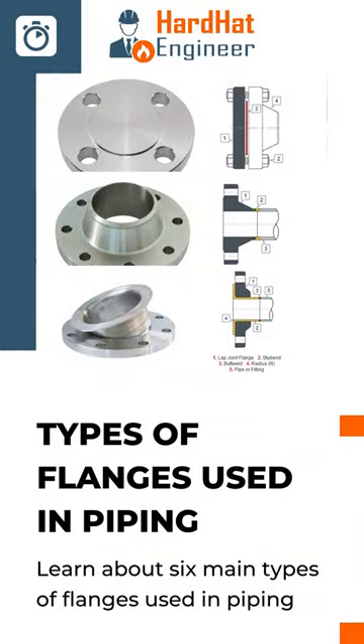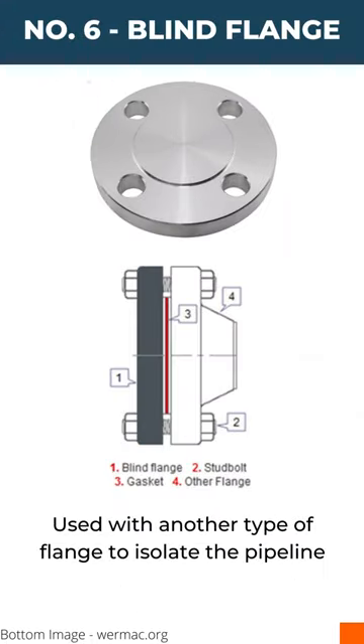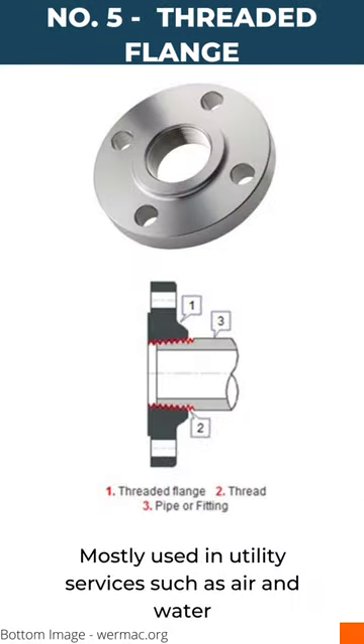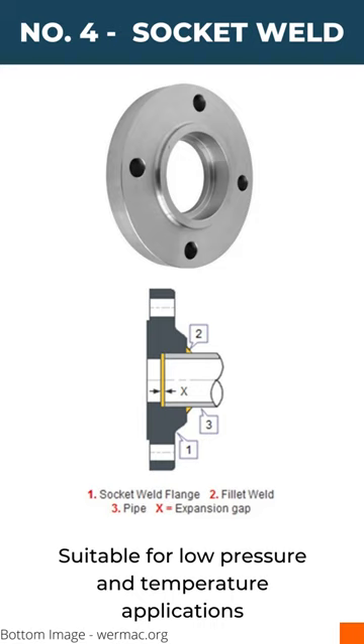Many types of flanges are used in piping, but these six types are the main ones. Number six is the blind flange — these flanges are used with another type of flange to isolate the pipeline. Number five is the threaded flange, which is mostly used in utility services such as air and water.